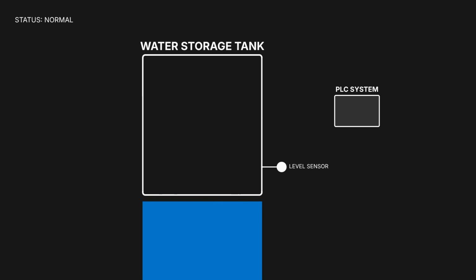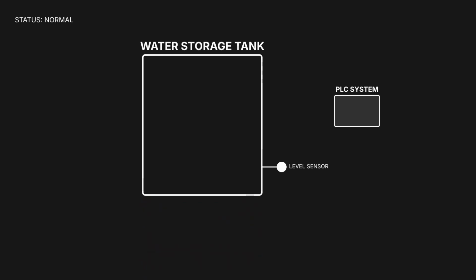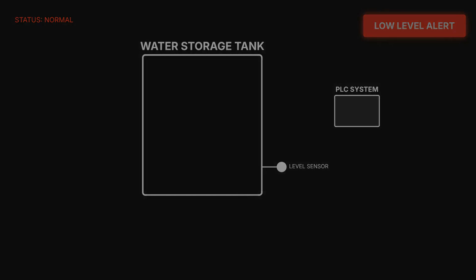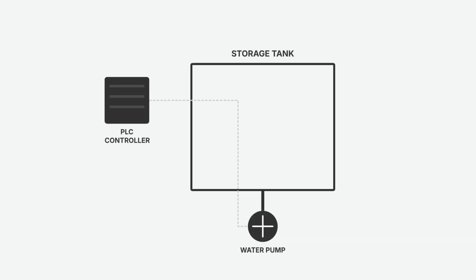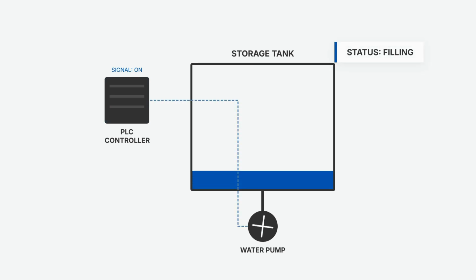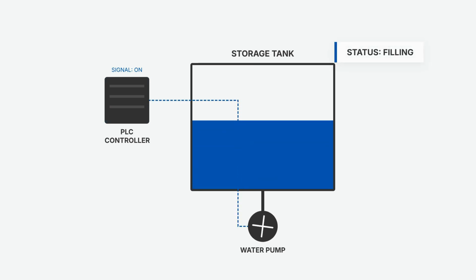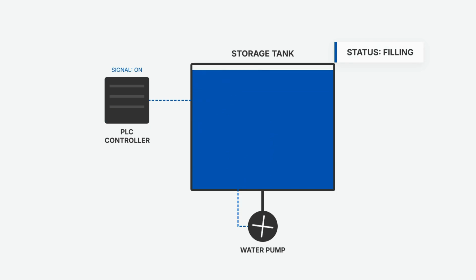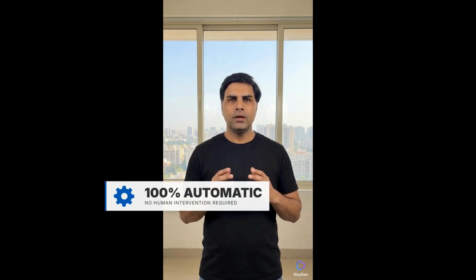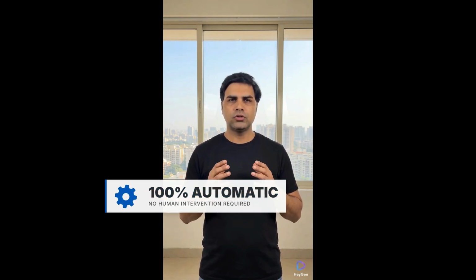Let's take a simple example. Imagine a water tank. A level sensor detects that the water level has dropped below a minimum value. The sensor sends this information to the PLC. The PLC processes the signal. Then it sends a command to start a water pump. The pump fills the tank. Once the tank becomes full, the sensor informs the PLC again. The PLC then stops the pump. This entire process happens automatically. No human intervention is required.